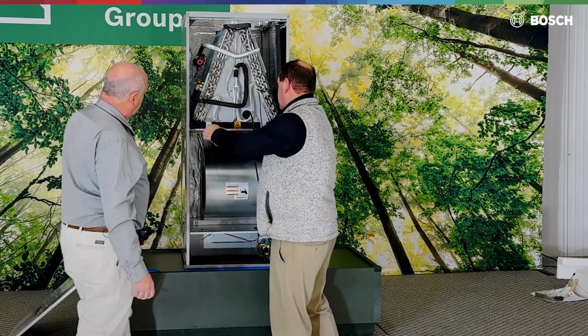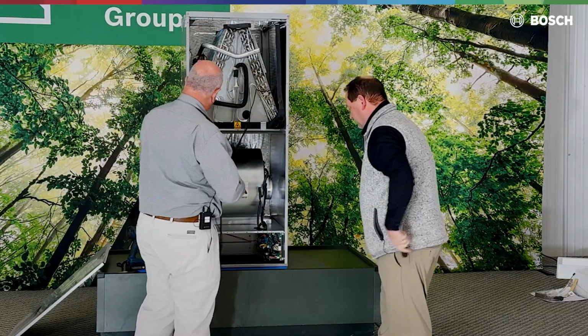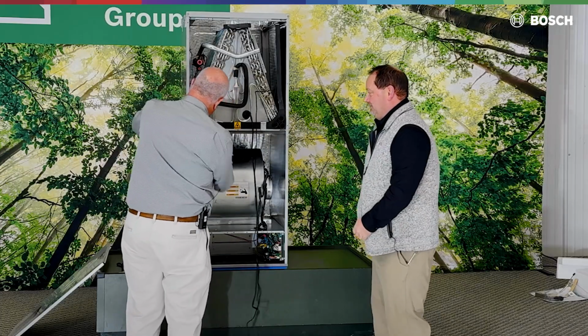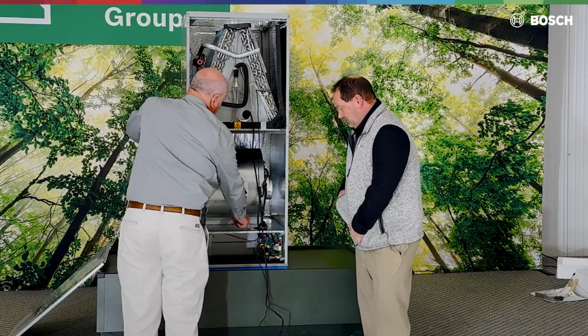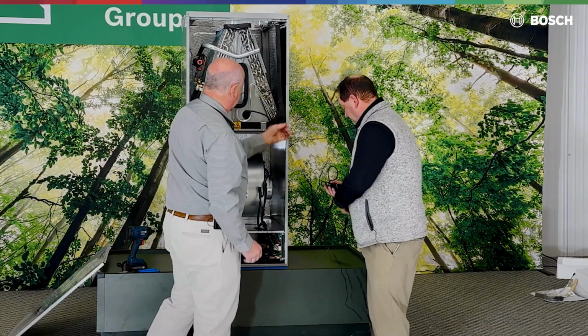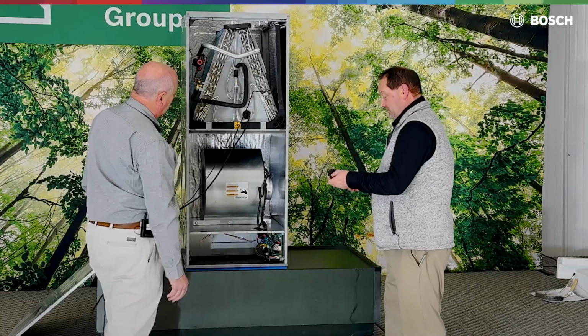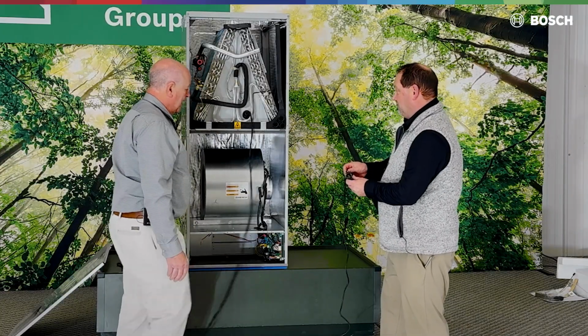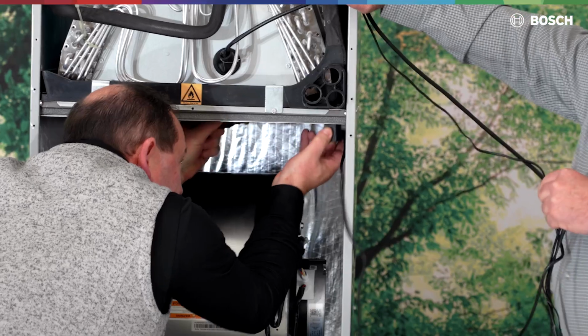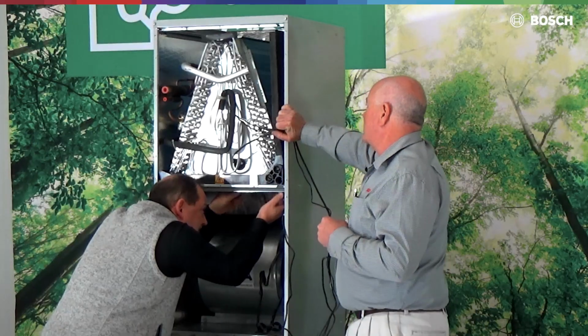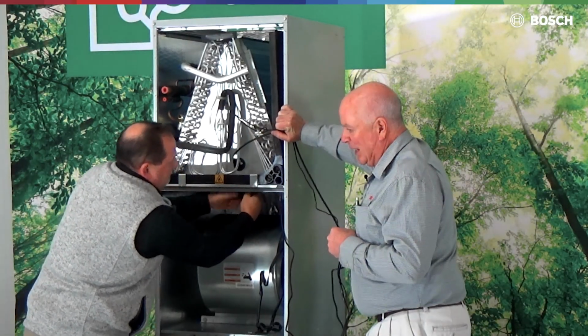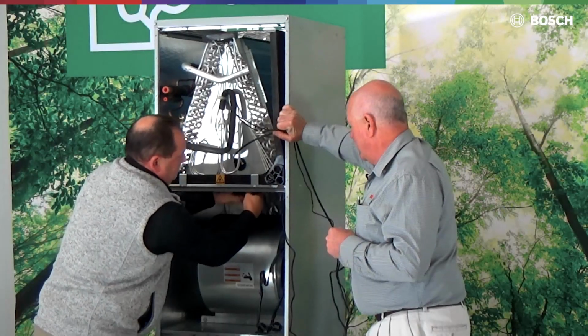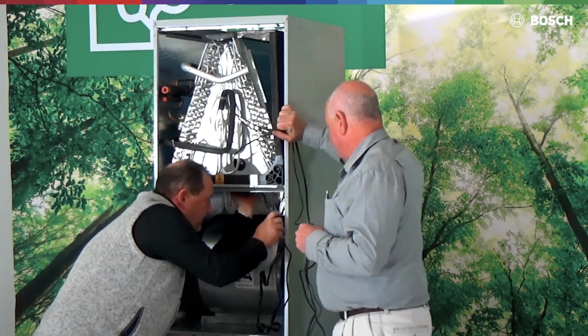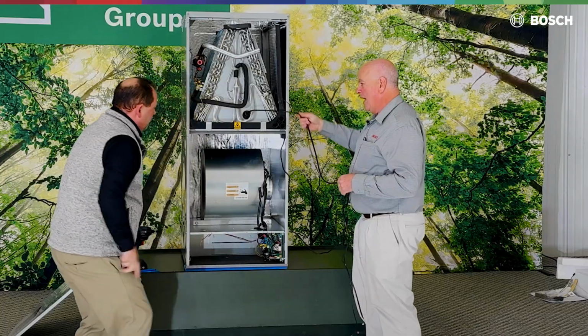So when it comes time to route these wires down, we're going to route these wires down along the pan, under this edge, and into the board. They don't have to go out of the unit. They can be done internally, and we will mount this coil A2L sensor as well. Why are we putting the A2L sensor underneath? Because refrigerant is heavier than air. It'll settle. We want to pick up that concentration level. Okay, looks like it's in place. Are you happy? I am.